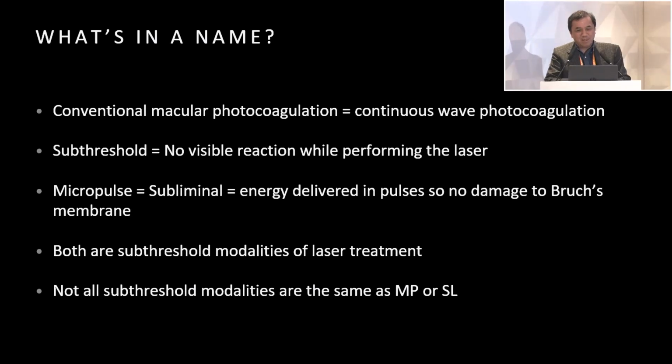So what's in the name? So when we talk about conventional macular photocoagulation, we're referring to continuous wave photocoagulation. That means that when you press down the pedal, and remember there's a time and also the power, once you press it down, then you're going to deliver the power for the entire time. The subthreshold means that there's no visible reaction while performing the laser.